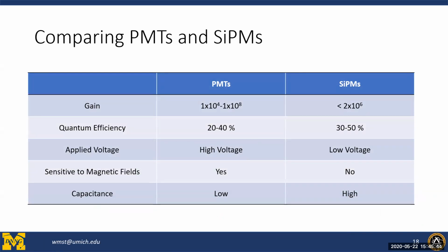We'll do a comparison between these two real quick, but two quick questions. Question on PMTs: what happens if a photomultiplier tube is left at high humidity for a long period of time? Very good question. I am not familiar with any response of photomultiplier tubes themselves to humidity. Generally, photomultiplier tubes are very temperature dependent, and they are also very sensitive to magnetic fields. I have not seen any literature to suggest humidity substantially affects them. I would expect humidity would more so affect the scintillator that it's coupled to, but good question.